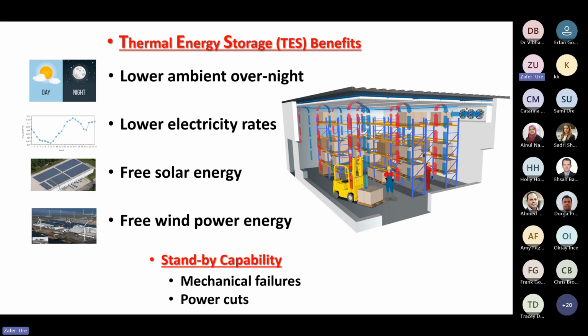But thermal storage also offers various advantages. First of all, if we're capable within the design of running the machine overnight at 10 to 15 degrees C lower nighttime temperatures, you will be physically saving 20-30% of your kilowatt-hour electricity consumption on mechanical refrigeration.